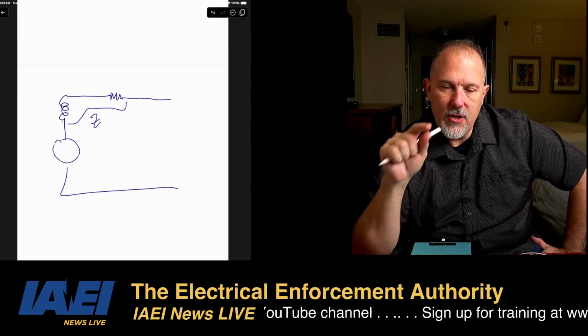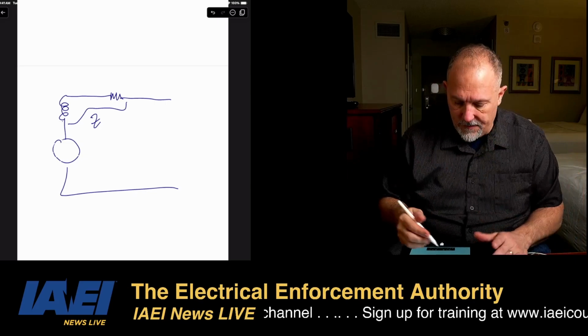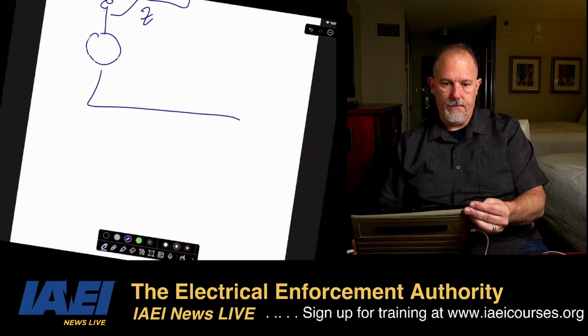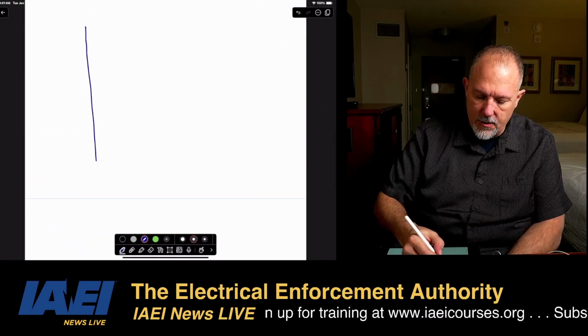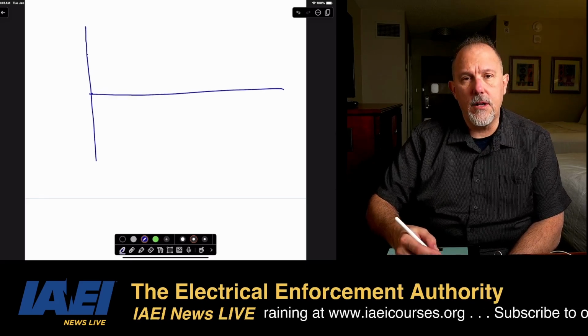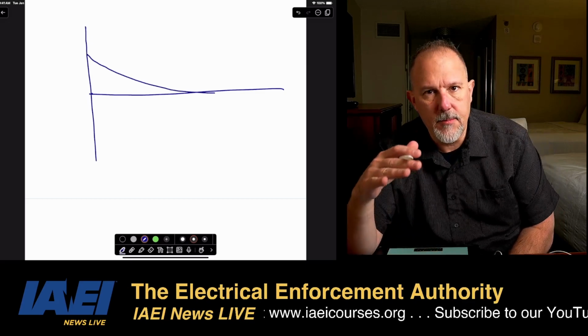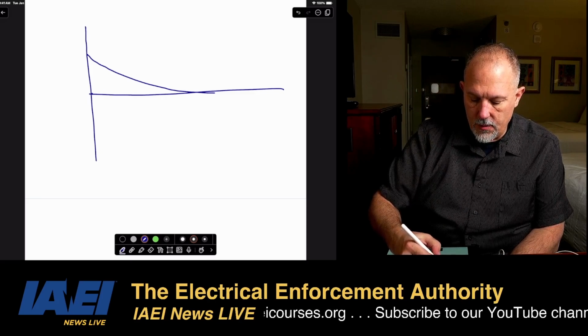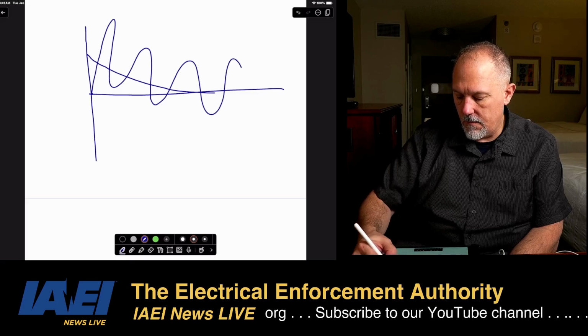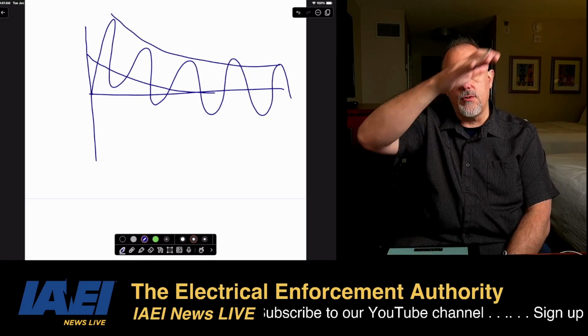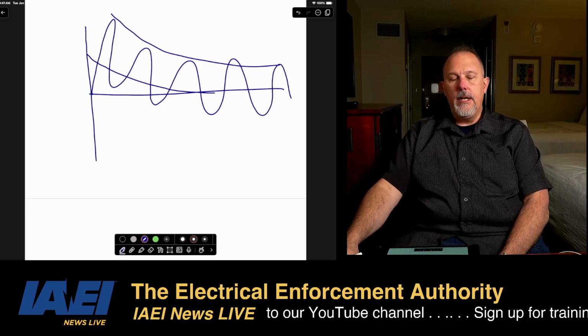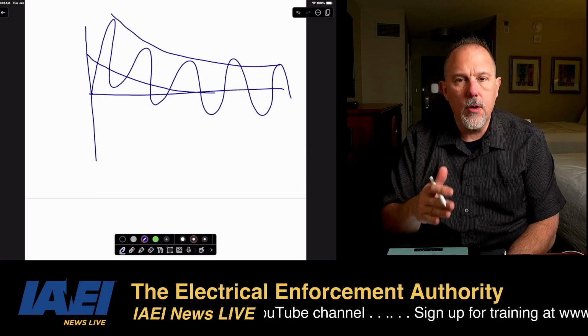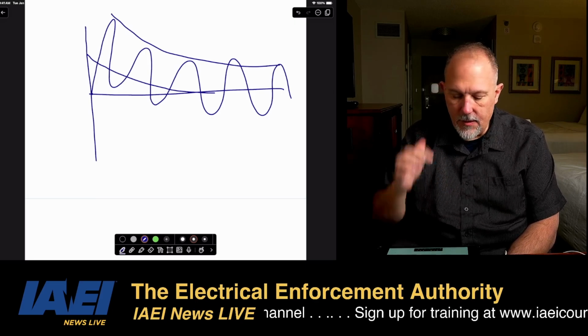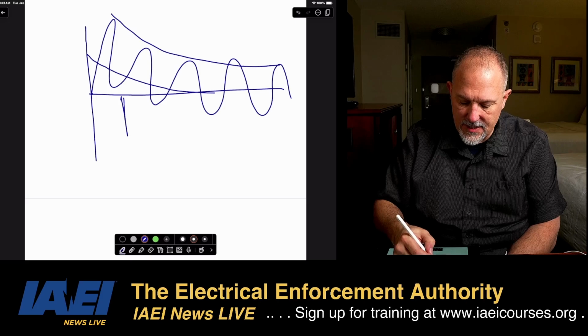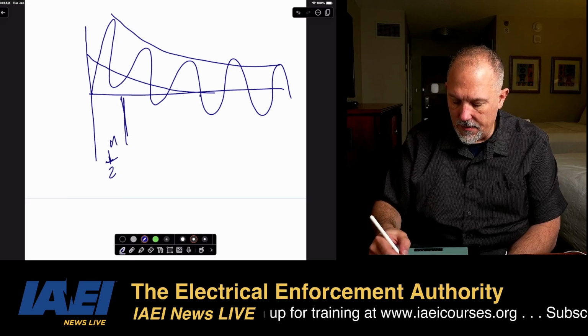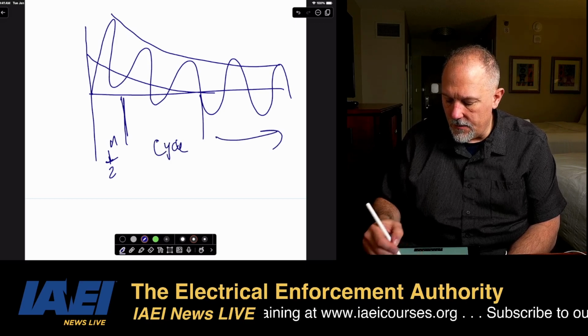Think about a waveform. So let's do it this way. There we go. So if we think about a fault current waveform, it follows what we call a DC offset, and that will be determined by the X to R ratio. And your fault current will do this. So it has an asymmetrical slope down. And your generator output will do the same thing. Now, how do we calculate, say, this first half cycle, right? The first half cycle, and then maybe the next cycle or two, and then the rest of it.